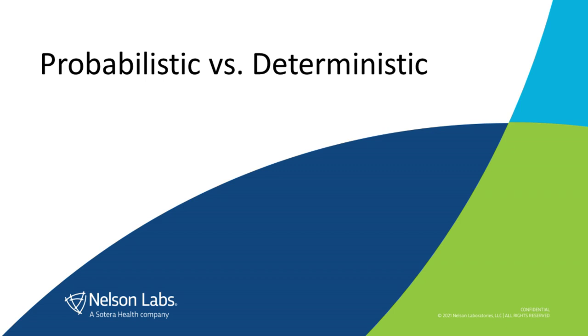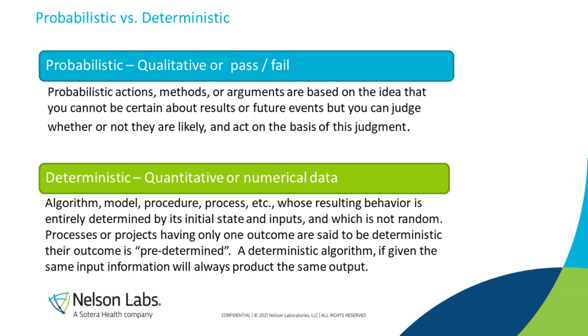USP 1207 divides CCI testing into probabilistic methods and deterministic methods. In simple terms, probabilistic methods are qualitative or pass-fail methods and are usually based on observations by humans. Deterministic methods are quantitative — there's a measured value generated by a machine. That's the basic difference between those two.